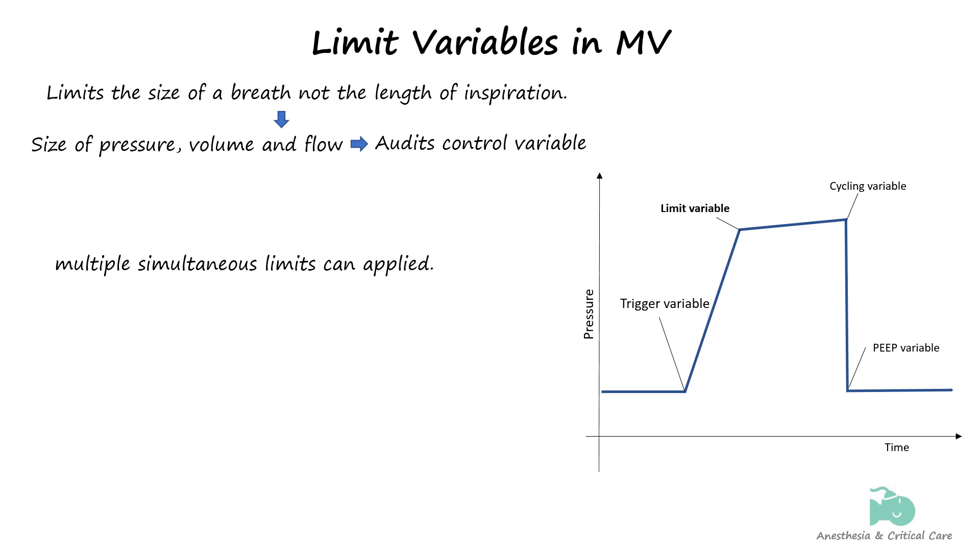In other words, a limit variable is the maximum value a variable can attain during inspiration to prevent lung overdistension, and it refers to the inspiratory phase only.